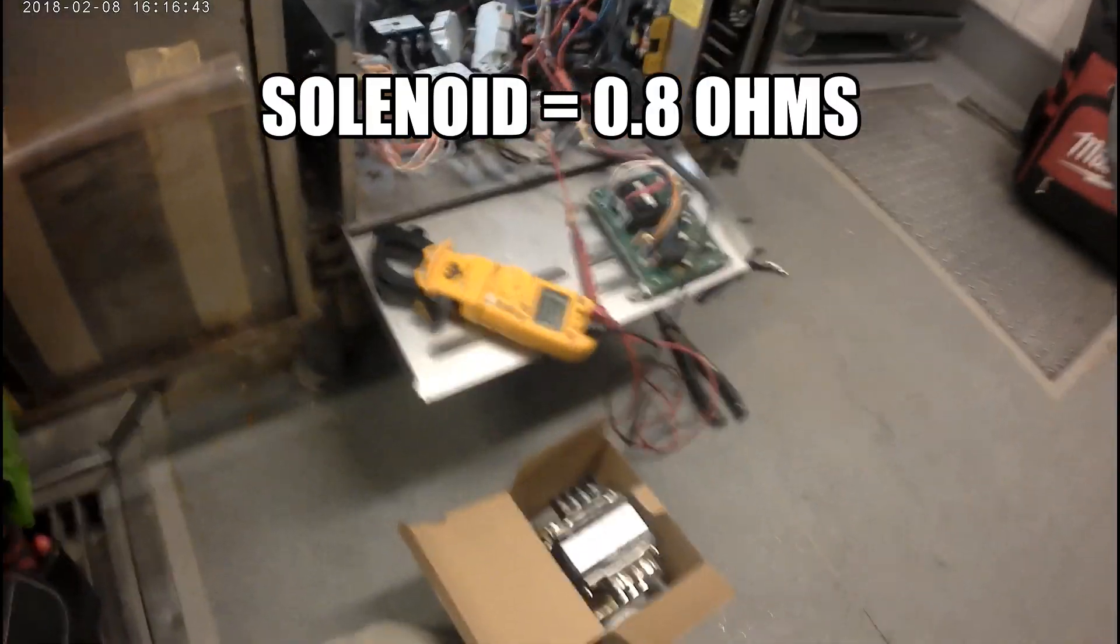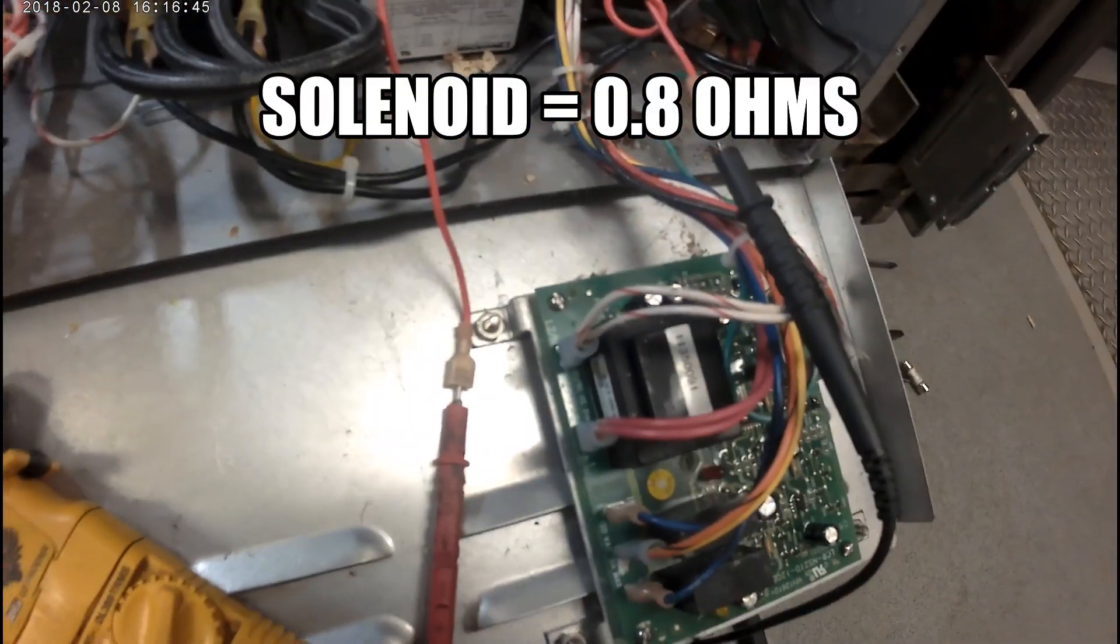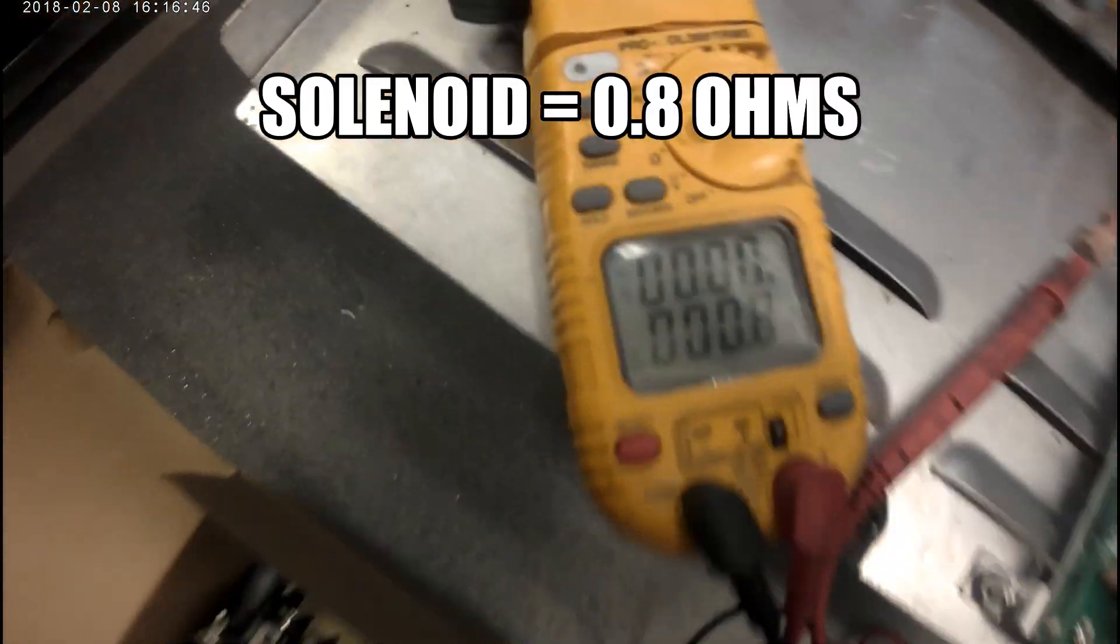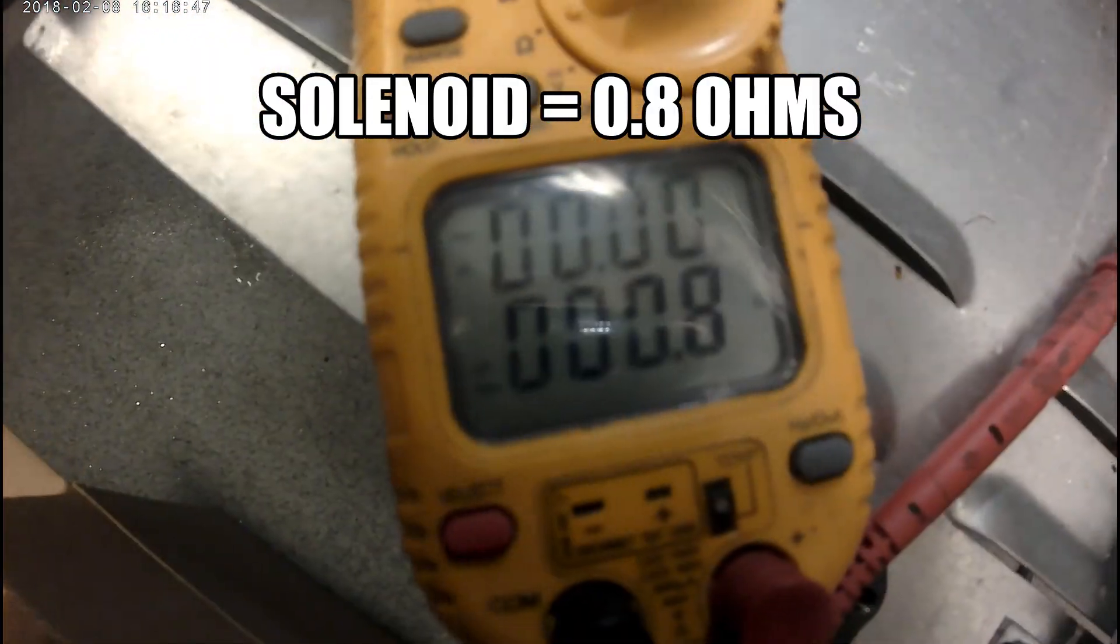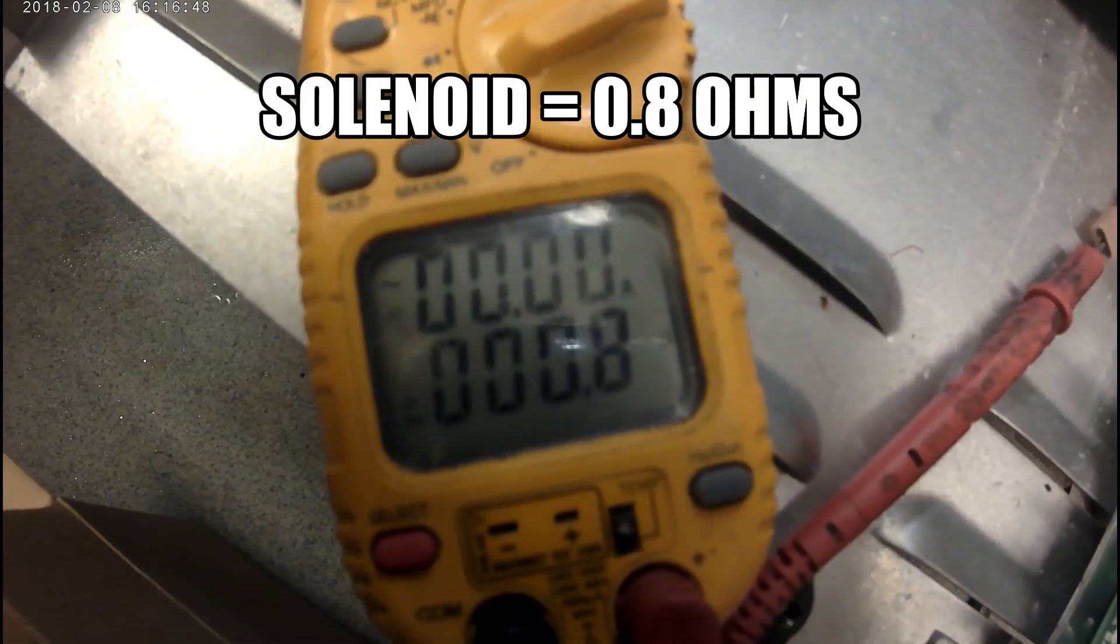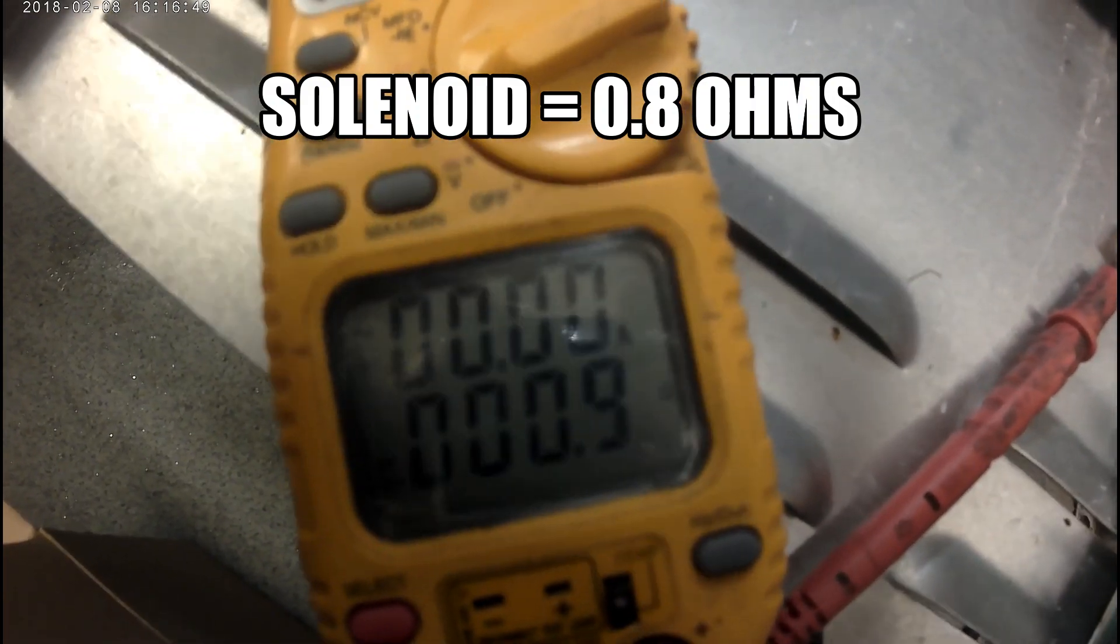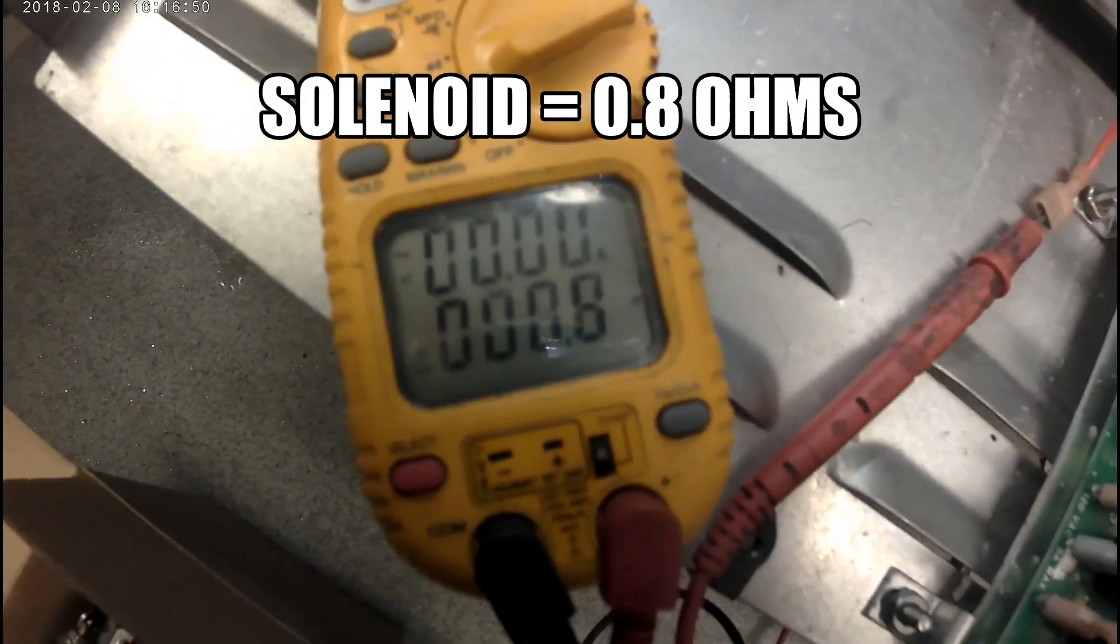Then I ohmed out my drain valve. I'm getting 0.8 ohms on it. I disconnected both wires from it.